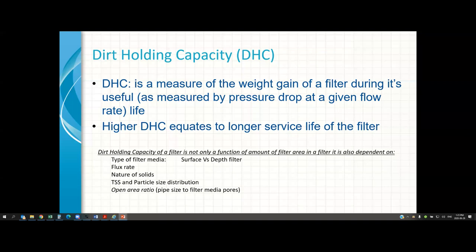The open area ratio: for example, if we purchase a two-inch basket strainer with one-eighth inch perforation, the basket should have thousands and thousands of holes. If it has only 10 or 20 holes, you have less open area for fluid to pass through — the strainer basket will plug very quickly and you might have to change it multiple times per shift. The ideal open area ratio is one to four: the total area of all open holes in the basket, especially for surface filters, should be at least four times the open area of the inlet and outlet.